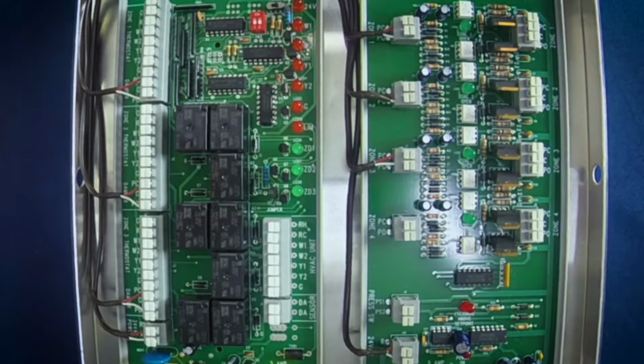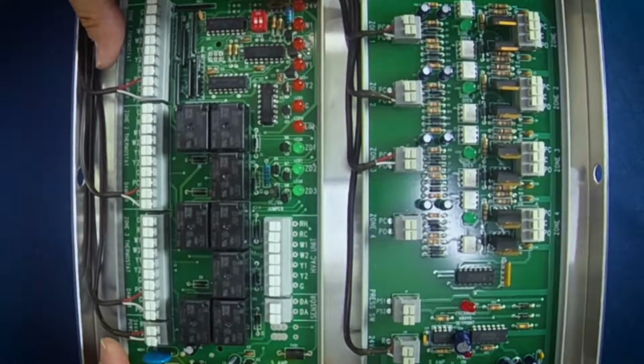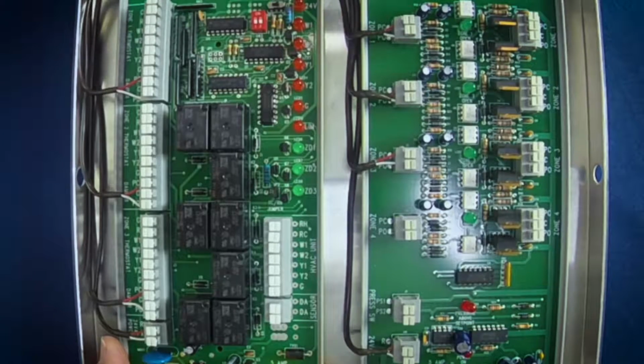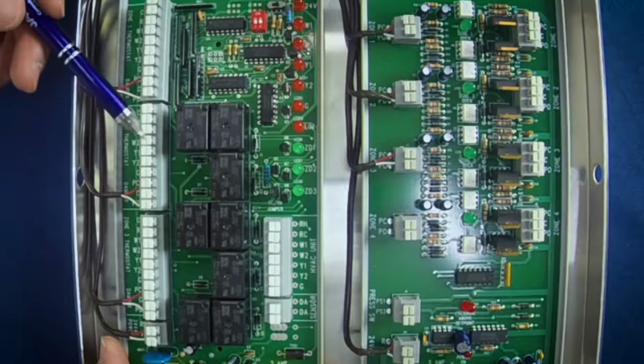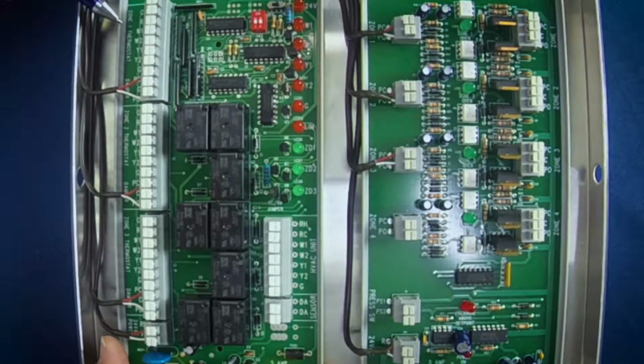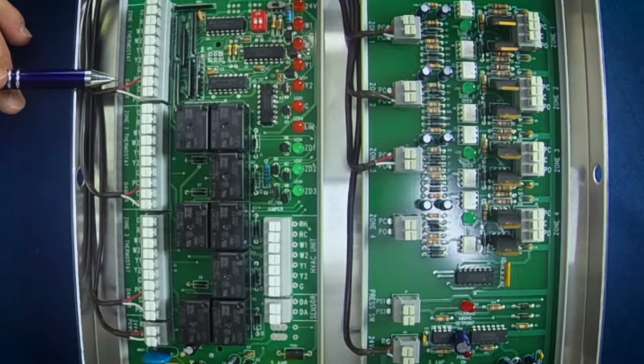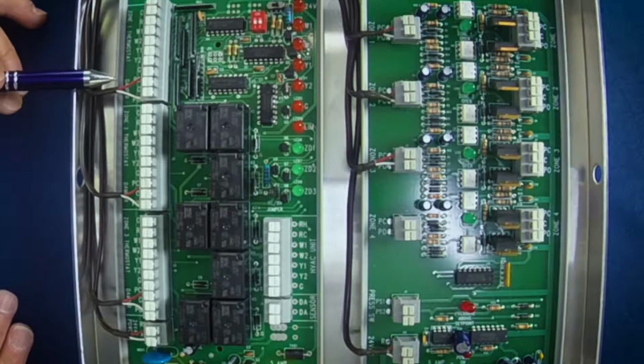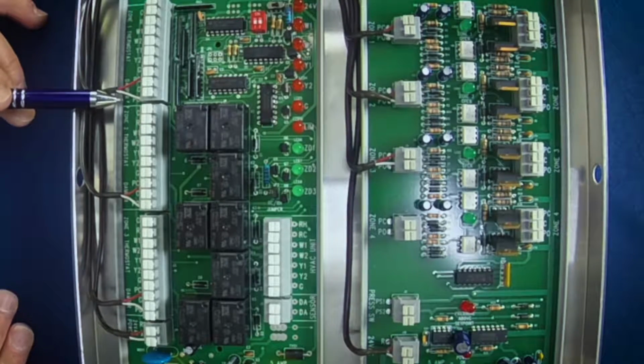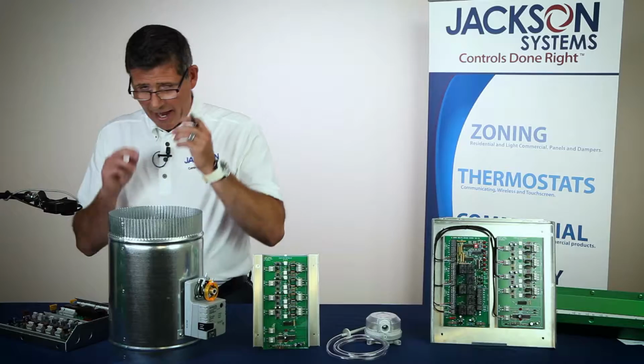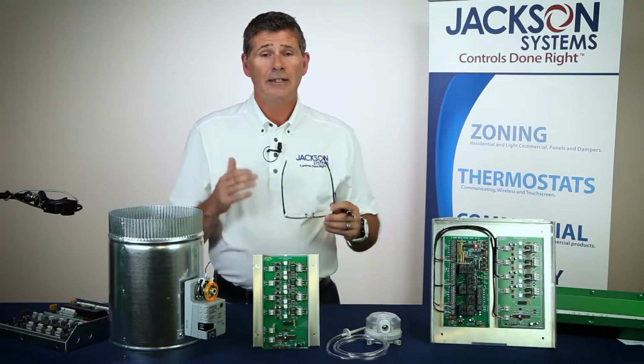And the first thing you're going to notice, obviously, let's just take a look at the Z300 panel. You're going to have your zone 1 and zone 2 and zone 3. This is where you're going to wire in your thermostats as normal. And then down here at the bottom, you're going to have the dampers set up. So now you're going to notice something right off the bat. You're going to see that we only have 2 wires. Now with this system, you have to use a 3-wire damper.